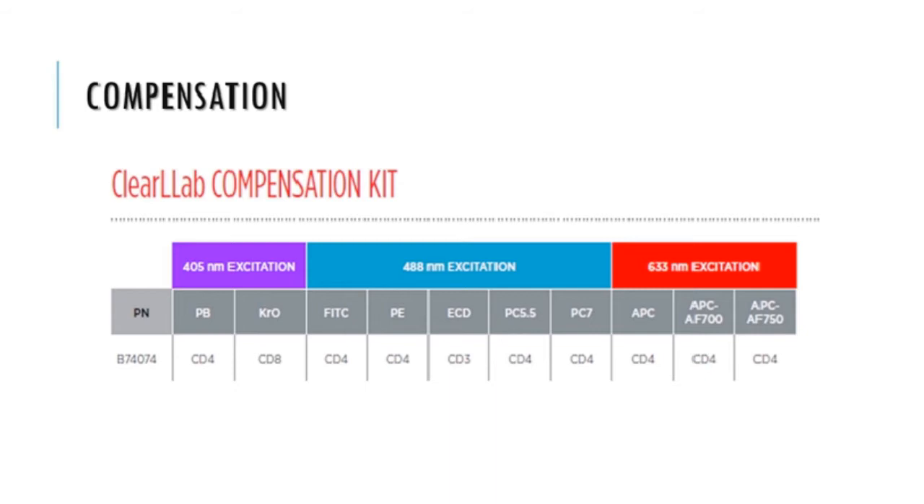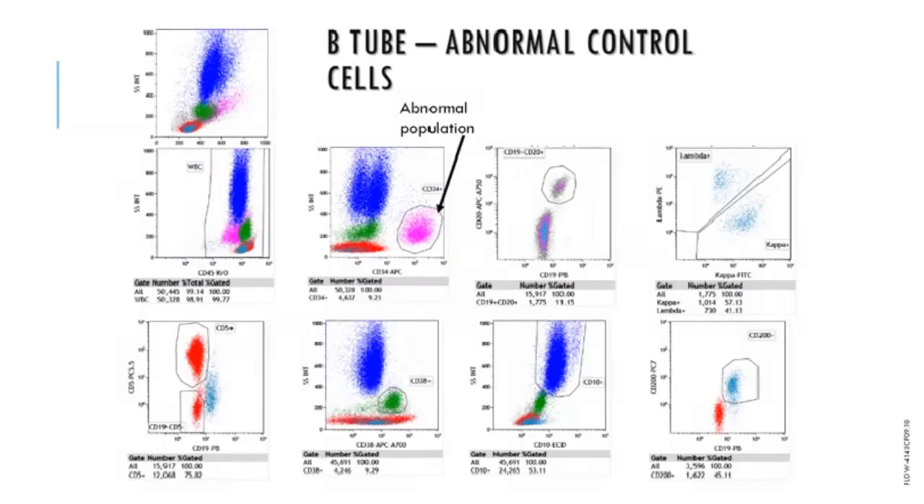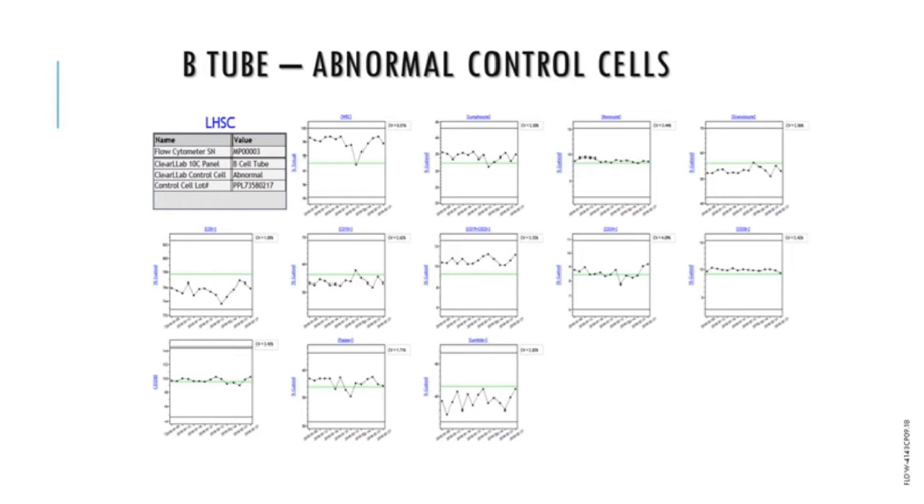Using individual verified tubes for each of the panels allows customization of compensation for each tube. There are ClearLLab control cells for both normal and abnormal populations. This is an example of the abnormal cell control stained with the B cell tube — note a population of approximately 9% which is CD34 positive on the side scatter versus CD34 plot, and the normal B cell population clearly expressing CD19, CD20, CD200, and Kappa/Lambda. Consistent colors are used throughout each tube: granulocytes are blue, lymphocytes red, monocytes green, the CD45 dim population is purple, and where appropriate B cells are orange. Levey-Jennings charts automatically track the QC results for each tube over time for all key populations, which moves flow cytometry quality assurance for leukemia and lymphoma in a very positive direction.